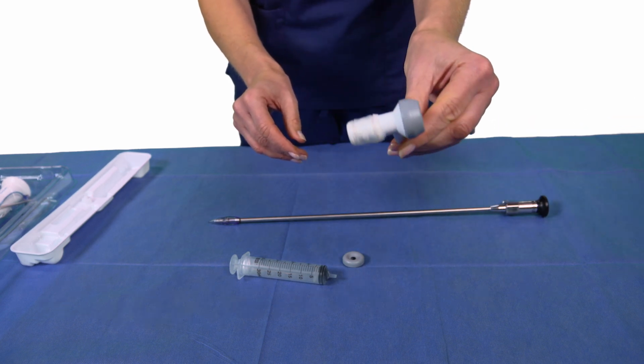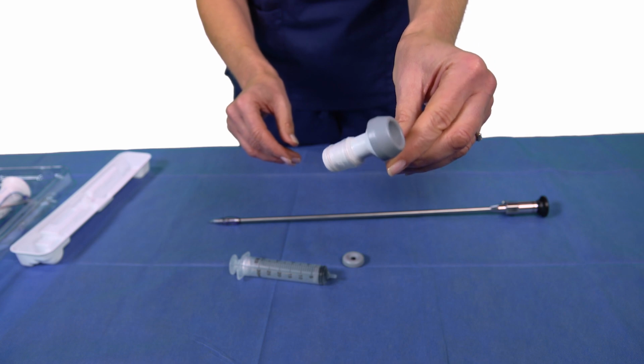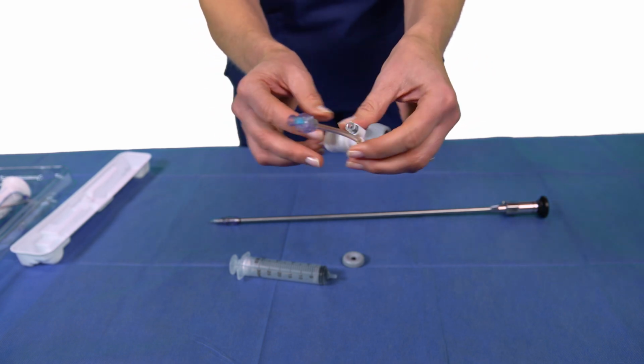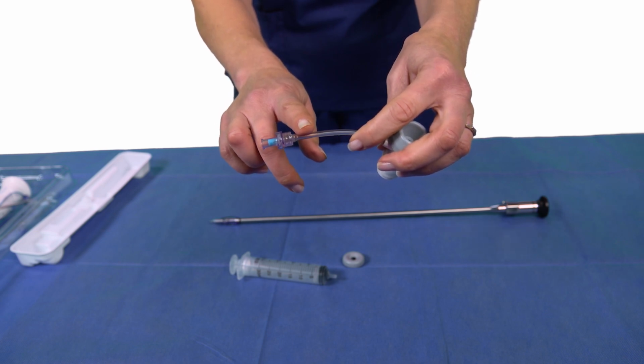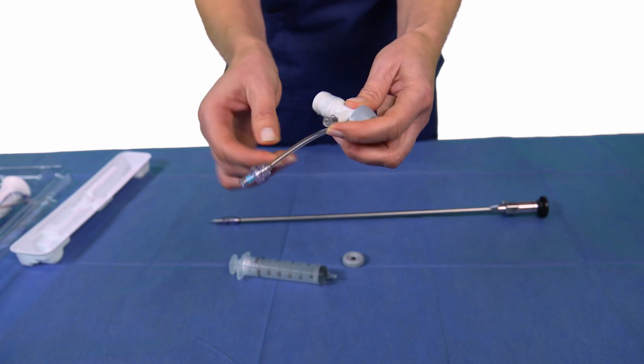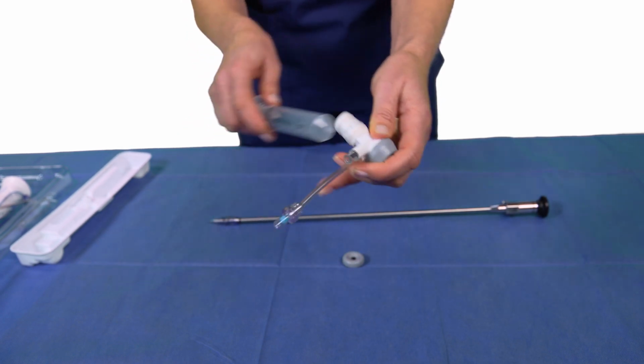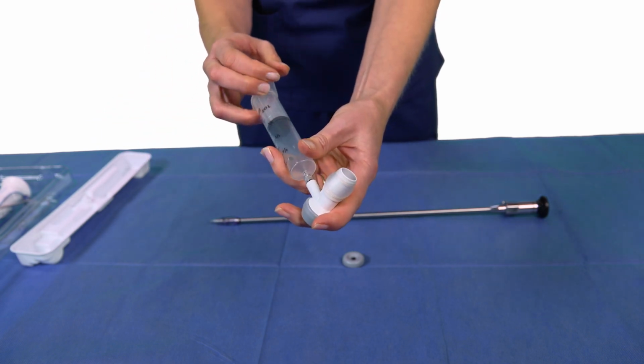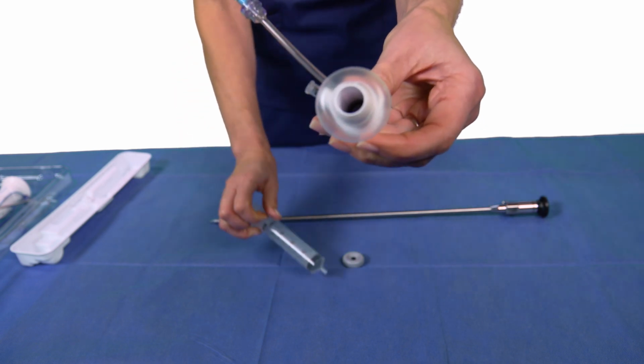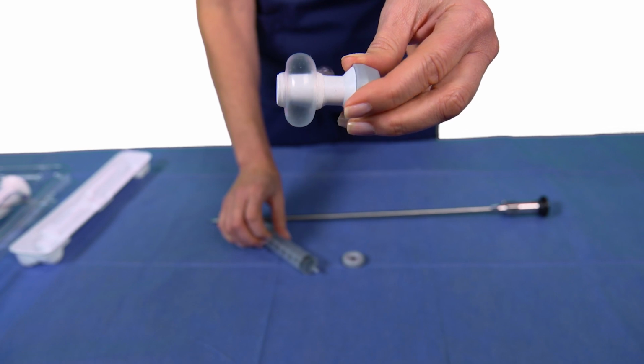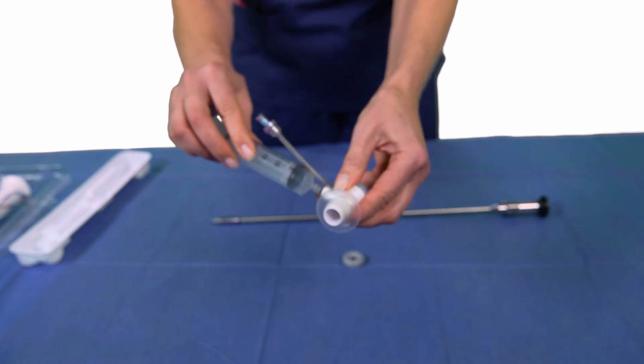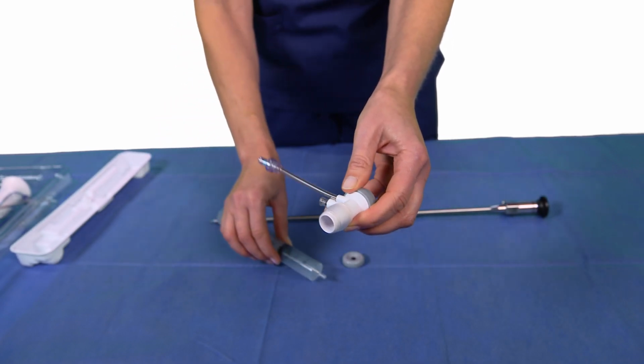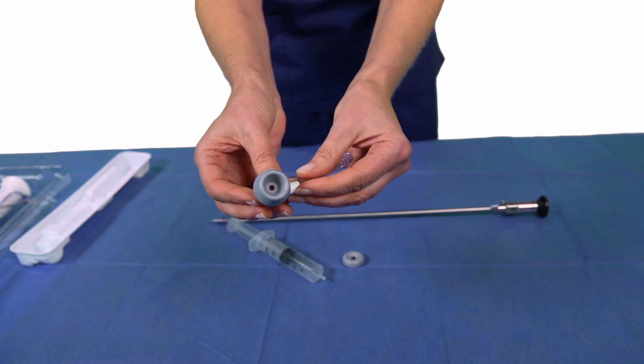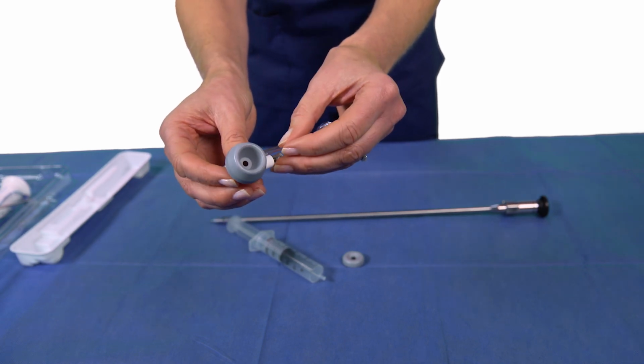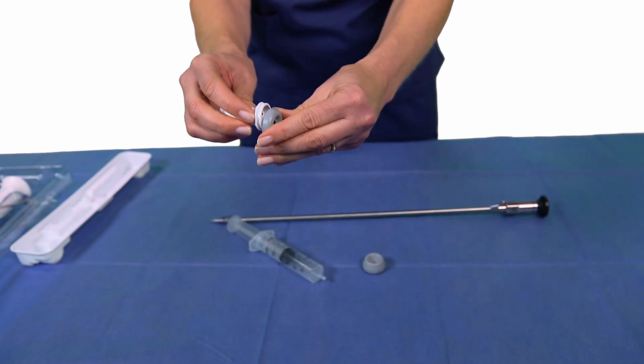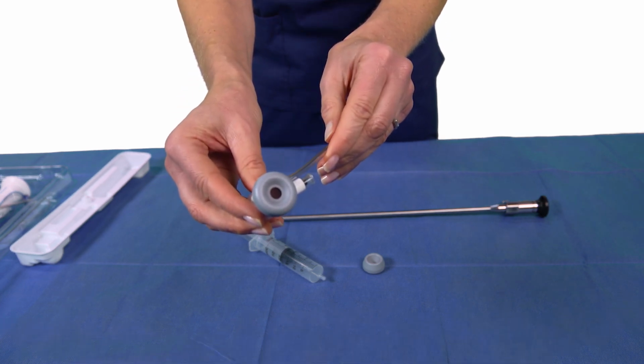The blunt tip trocar goes within the incision to create a seal for the CO2 tunnel. It has a clear tubing for proximal CO2 insufflation with a one-way valve. It also has a port to inflate the balloon. The balloon can be inflated with up to 25 cc's of air to create a better seal on the incision to maintain CO2. The BTT is used for both dissection and transection. During dissection, the smaller holed endoscope seal will be used. And during transection, the larger hole cannula seal will be used.